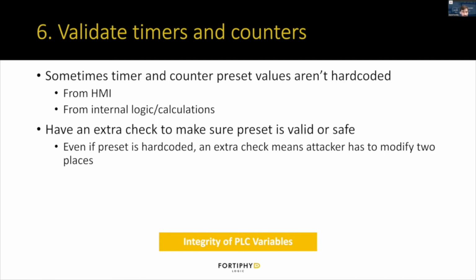The next practice is validating timers and counters. Sometimes timer and counter preset values aren't hard-coded. Maybe they're coming from the HMI, maybe they're coming from internal logic and calculations. And so it can be good and helpful to have an extra check to make sure that that preset value is valid or safe. Even if the preset is hard-coded, having an extra check in there does make it slightly harder for the attacker, meaning they have to modify two places in the logic to maybe cause problems instead of just the one.